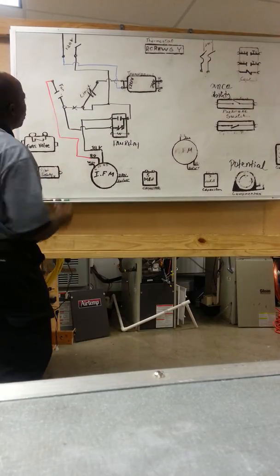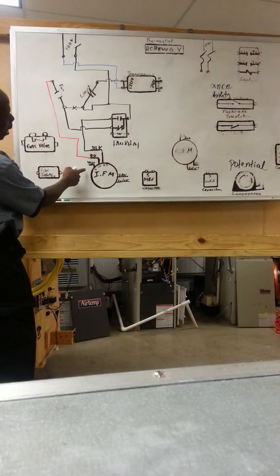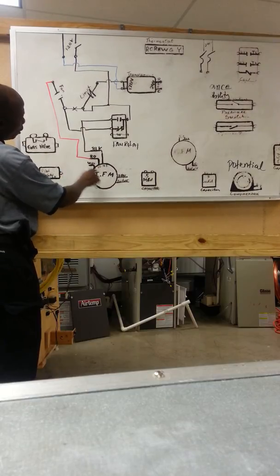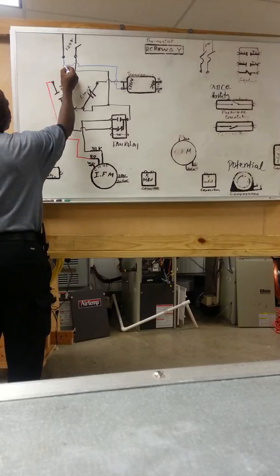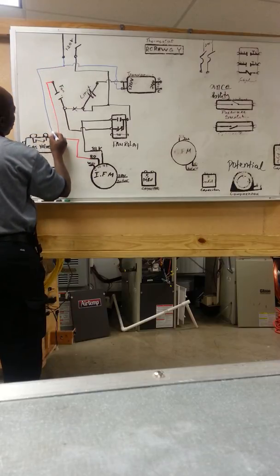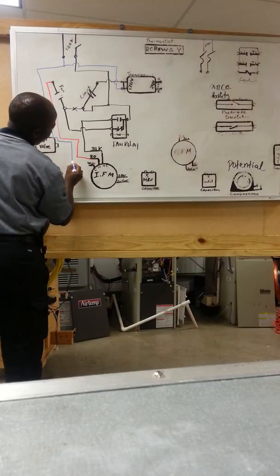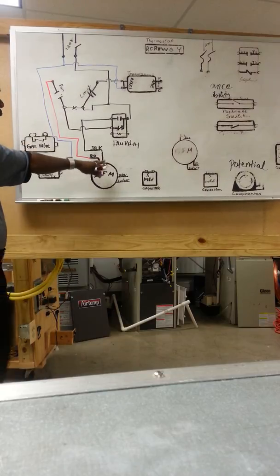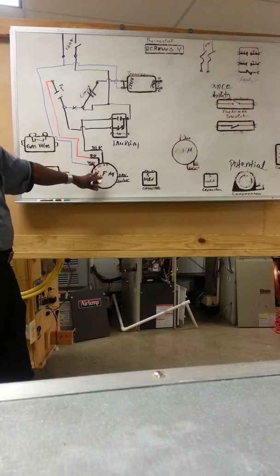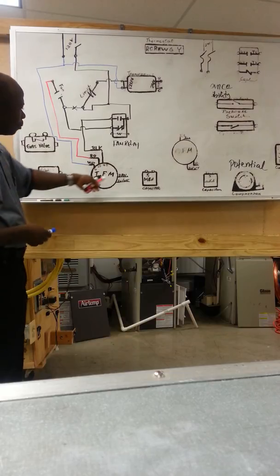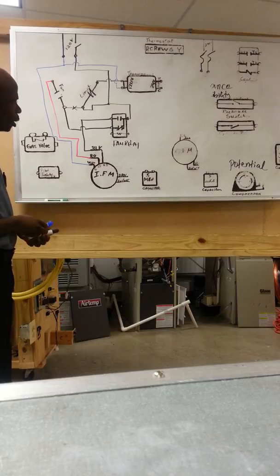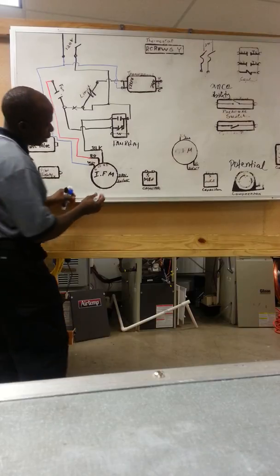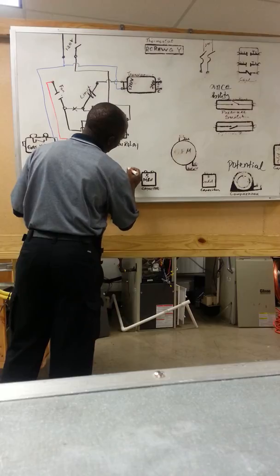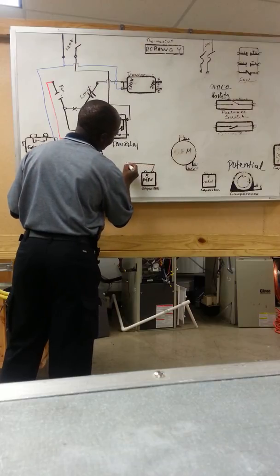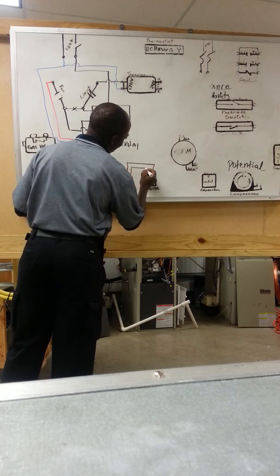Okay? So since we have 120 volt going to the transformer, and we have the indoor fan, it's almost done. We're going to also complete the polarity by bringing in the neutral to the fan white. Now this fan completely has 120 volt wiring done. All we have to do now is to complete the capacitor, which is 5 microfarad, to run this fan. So I'm going to get a brown wire from here onto my capacitor, another brown wire from here to the capacitor. Now this blower is actually ready.